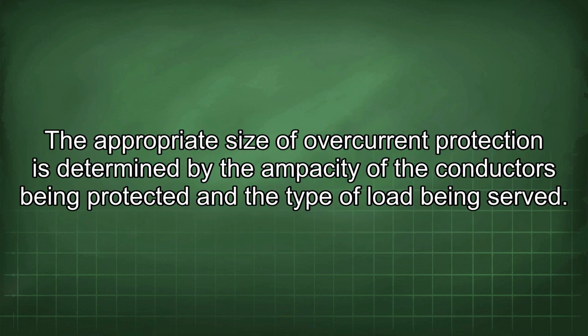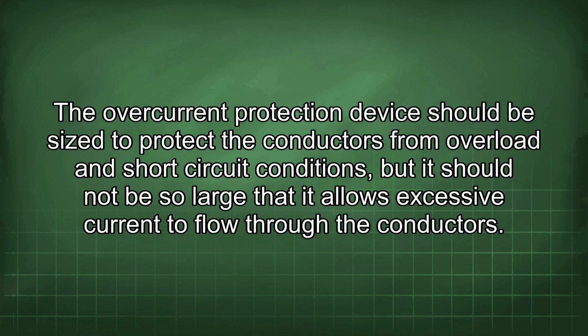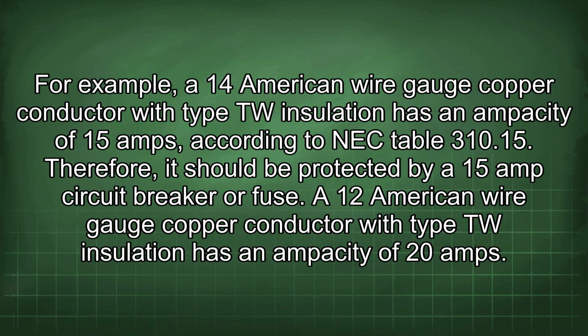The appropriate size of overcurrent protection is determined by the ampacity of the conductors being protected and the type of load being served. The overcurrent protection device should be sized to protect the conductors from overload and short-circuit conditions, but it should not be so large that it allows excessive current to flow through the conductors. For example, a 14 American wire gauge copper conductor with type TW insulation has an ampacity of 15 amps according to NEC table 310.15. Therefore, it should be protected by a 15 amp circuit breaker or fuse. A 12 American wire gauge copper conductor with type TW insulation has an ampacity of 20 amps.